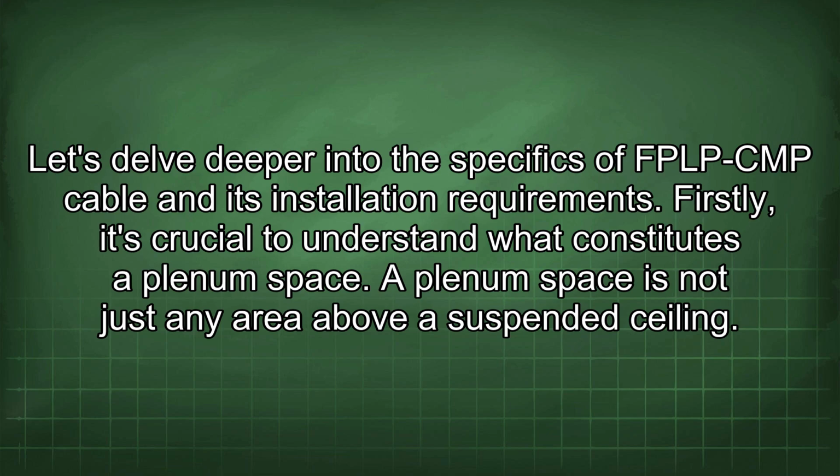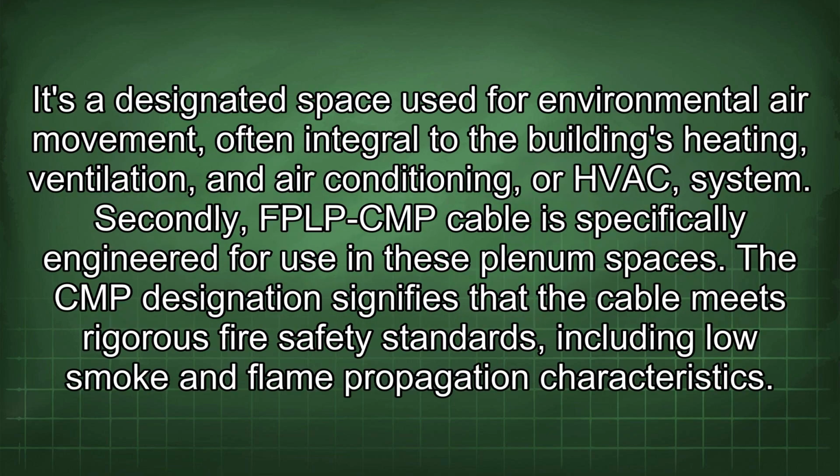Firstly, it's crucial to understand what constitutes a plenum space. A plenum space is not just any area above a suspended ceiling. It's a designated space used for environmental air movement, often integral to the building's heating, ventilation, and air conditioning, or HVAC, system. Secondly, FPLP CMP cable is specifically engineered for use in these plenum spaces.